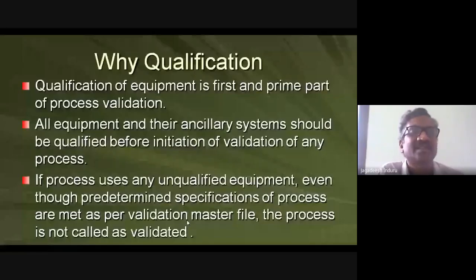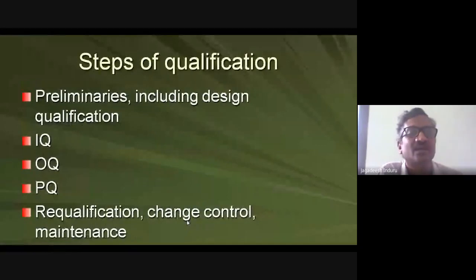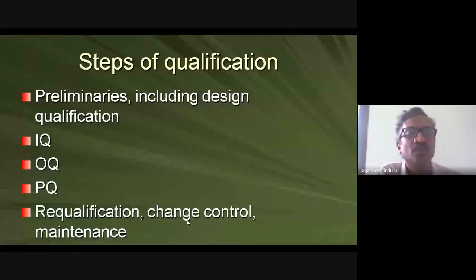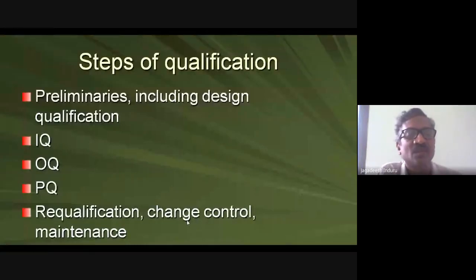The first thing is the preliminaries — brainstorming sessions and planning before doing anything. In that process you are going to get a Design Qualification, also called DQ. Next is IQ, OQ, and PQ — Installation Qualification, Operation Qualification, and Performance Qualification. After that comes re-qualification, change control, and maintenance.